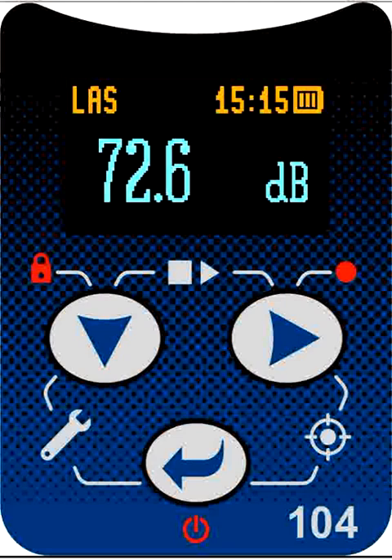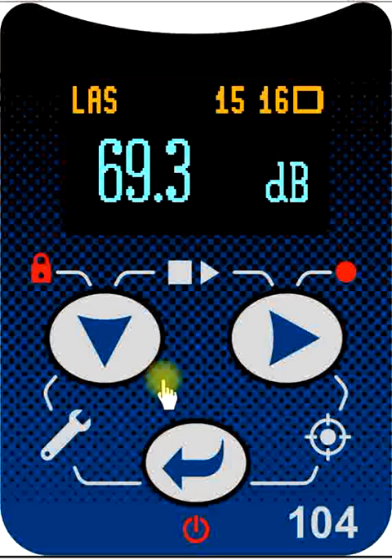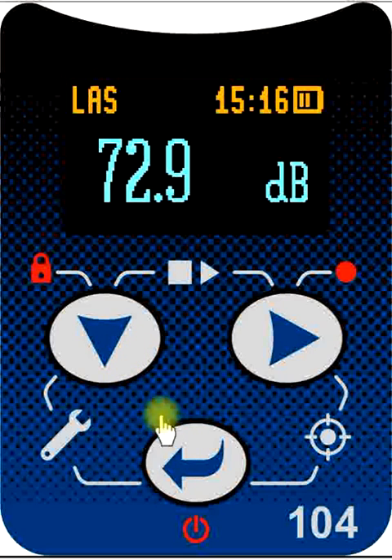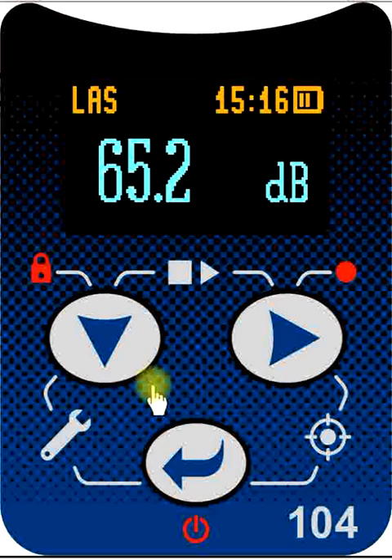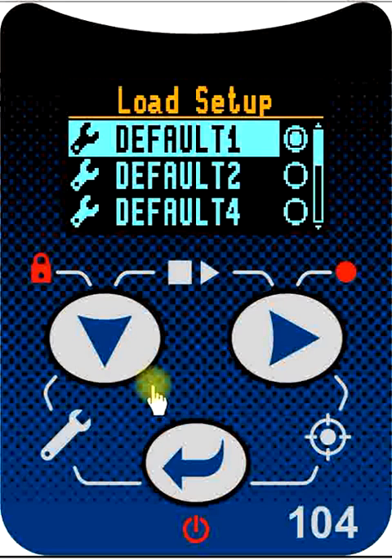If we want to change the configuration of the noise dosimeter to perform a slightly different task from the one that it did last time, we have the means to do this using the down and the enter buttons that will bring up a setup menu for us. If you press these two buttons and hold them for 3 seconds, the setup menu is displayed and a list of previously stored setup names is shown in the display.